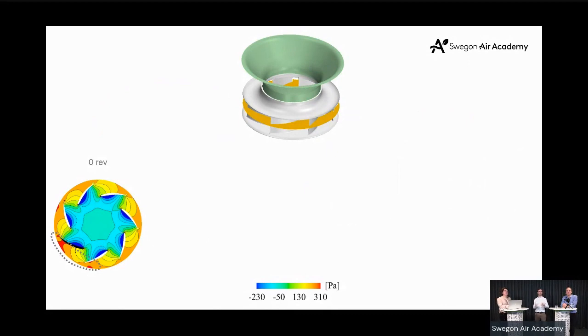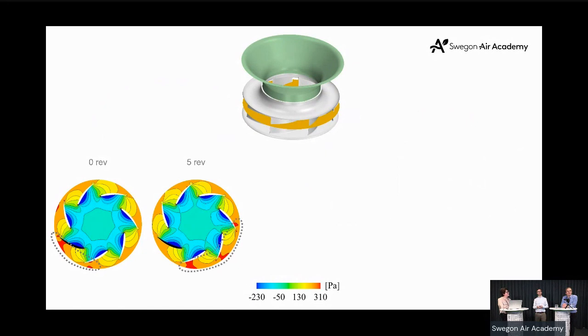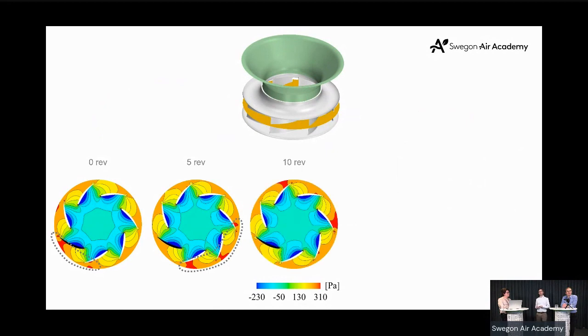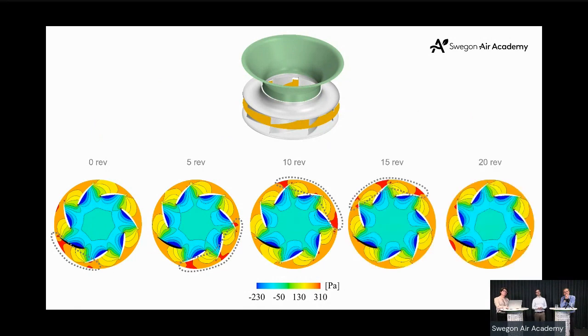It's a high pressure. Then we start to rotate this. So here we have 0 revolutions, and then we rotate it 5 revolutions. And we come to this, and we see that the high pressure region has moved a little bit. And after 10 revolutions, the high pressure region has rotated a half revolution. And 15, and then we go to 20 revolutions. And here the high pressure region is back at the same position as at 0 revolutions. So the high pressure region has rotated 1 revolution for 20 fan revolutions.